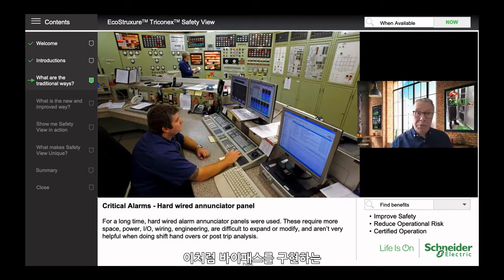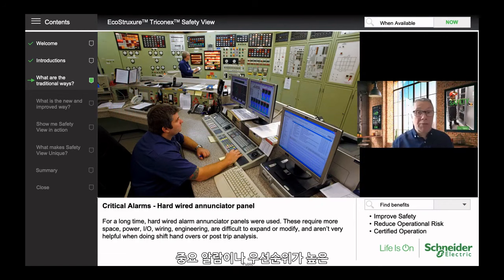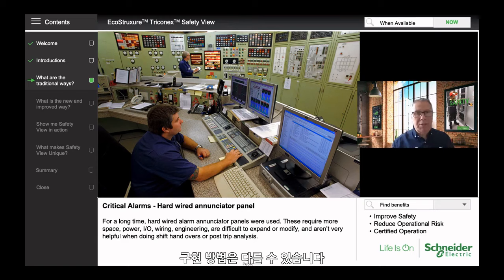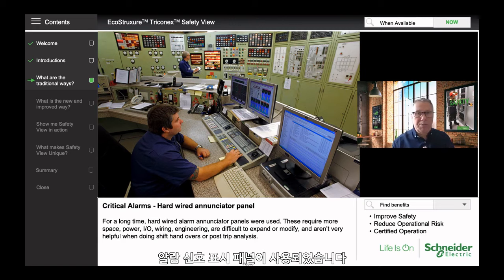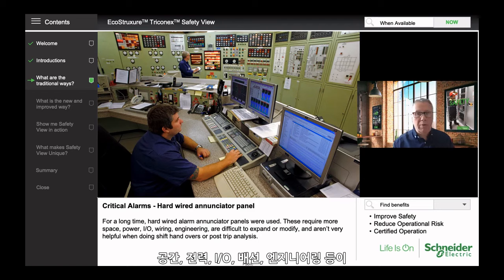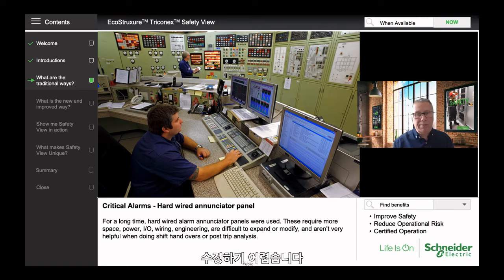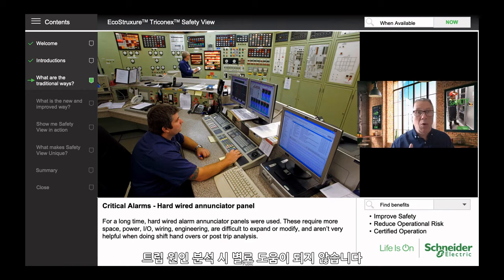It's the same for critical or priority alarms. There have always been these alarms, but how they are implemented can differ. For a long time, hardwired alarm annunciator panels were used. These require more space, more power, more I/O, wiring, and engineering, and they're difficult to expand or modify. They certainly aren't very helpful when you're doing a shift handover or having to do some form of post-trip analysis.